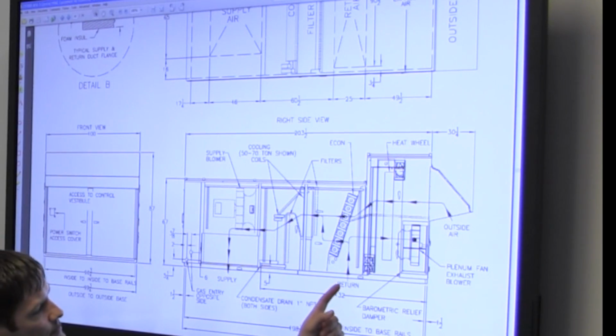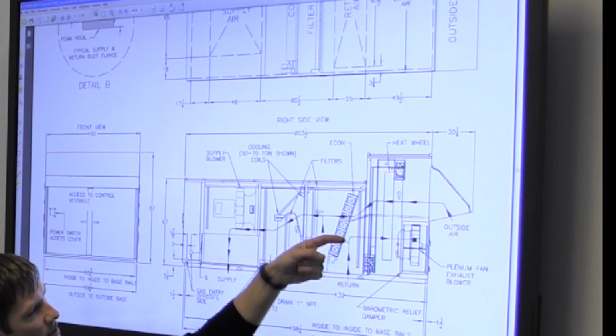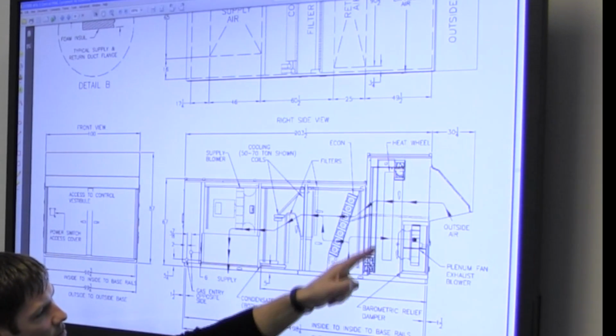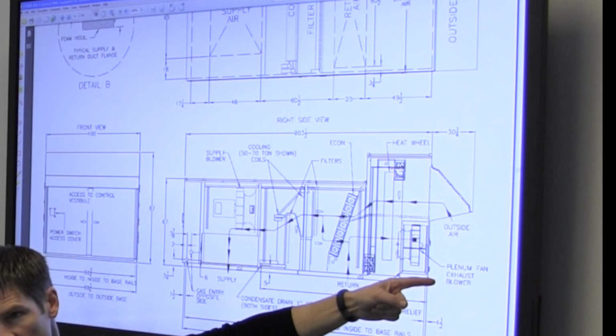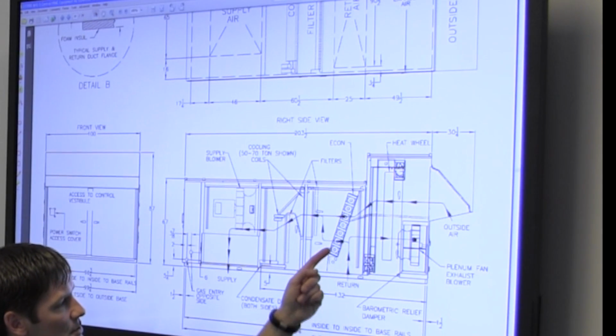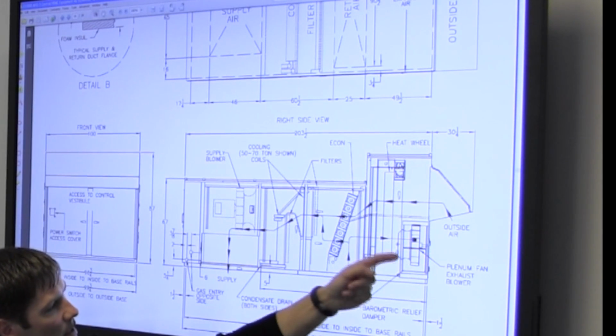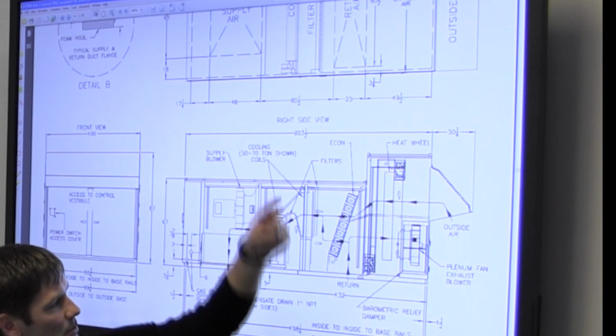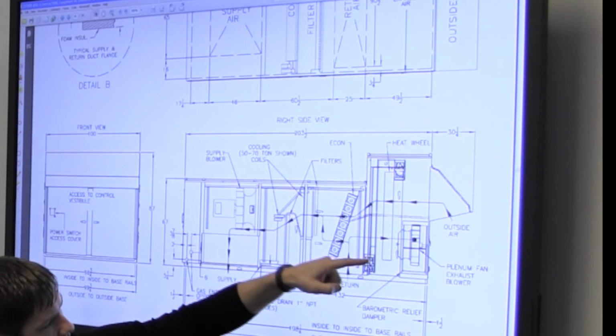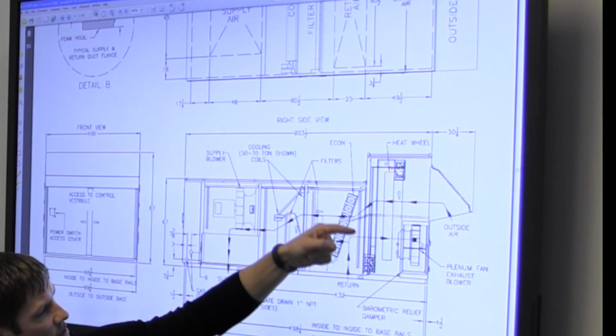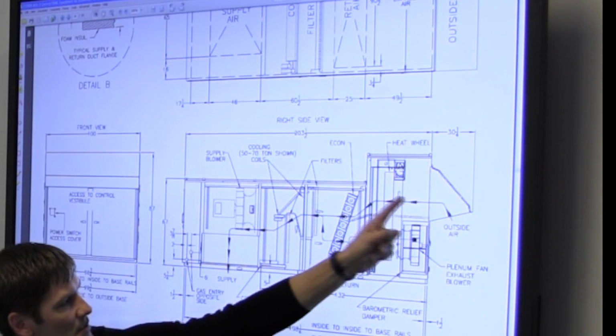But for the most part, this return air comes in, goes through the heat wheel, it's right here, and goes out that exhaust fan. So all it's doing is coming up, going through the wheel. It's heating this lower portion of the wheel. The wheel spins like this. It spins up and then transfers its heat to the fresh outside air.